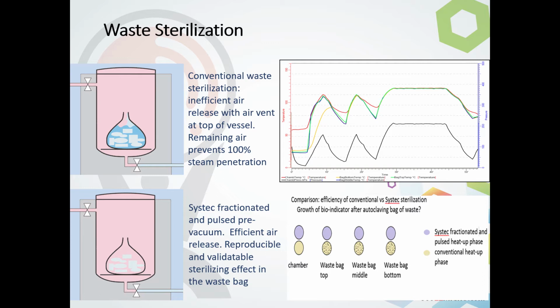In this diagram, what you will see is the differences in levels of where the chamber temperature is, the bag top, and the bag bottom. So you can see exactly what we're actually achieving through these pulses. We ran multiple temperature probes directly down into the bag, and you'll see after our third pulse, the top, bottom, and middle of the bag are the exact same. So that way we can know that we have achieved complete sterilization.